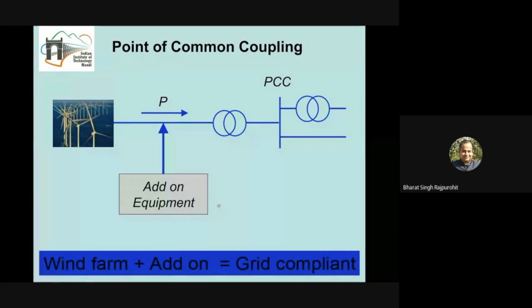But if they are not able to meet such grid codes, then it is expected that they will utilize some add-on equipment to provide support in addition to the renewable energy, to maintain the grid codes. These add-on equipment could be a simple energy storage if frequency stability or frequency regulation needs to be maintained, or it could be a static compensator, SVC, to maintain the reactive power. This is how add-on equipment can make the wind farm or solar farm grid compliant.